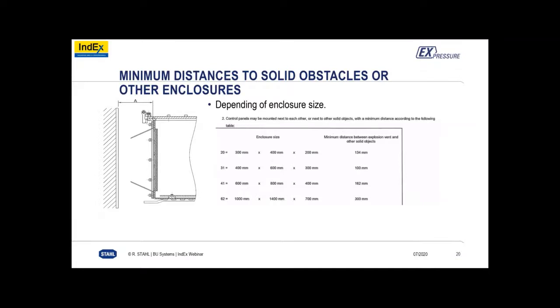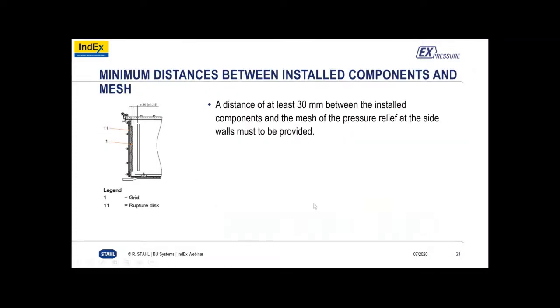Now, on the size of the enclosures, this is talking about the rupture disc clearance areas. If you have a size 62 enclosure, let's say, you have to have a minimum clearance of 300 millimeters. This is similar to flange type EXD boxes, where you have to have clearance of 10, 20, or 40 millimeters, depending on the type of gas group. For the rupture disc, you just have to consider what is in the certificate and their IOMs, installation, operation, and maintenance manuals. So it's just clearance on both sides of the cabinet, the enclosure. We'll go to the next one. It's an important consideration when installing this, because if the rupture disc is restricted, you're not meeting the certificate, and that is unsafe. It's obviously been tested specifically.